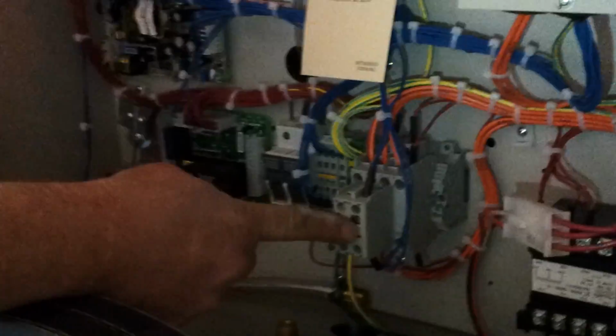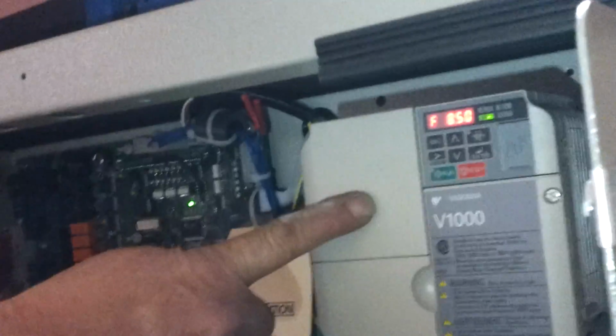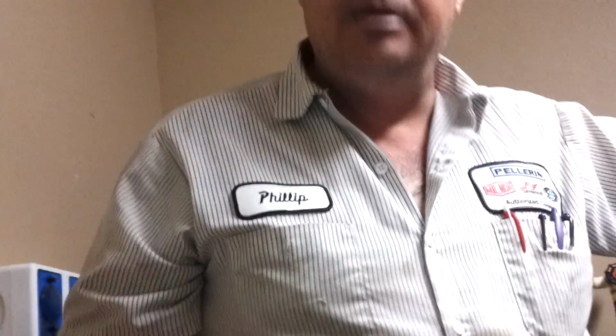When the door is shut, this contactor pulls in and this inverter is powered up. So when the door is open, this contactor drops out, the inverter powers down. So when you're not using the machine, you want the door to be in the open position.